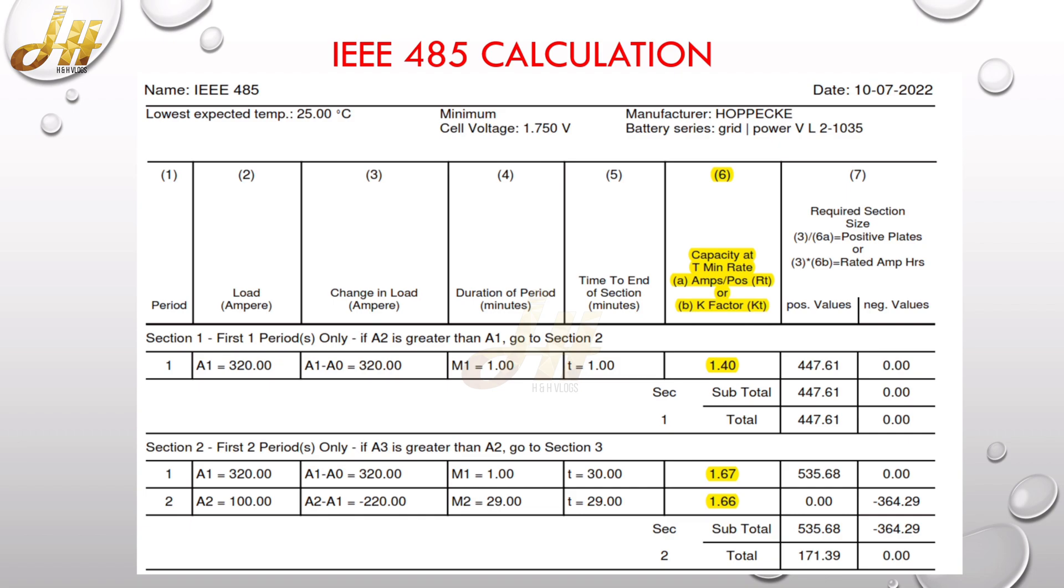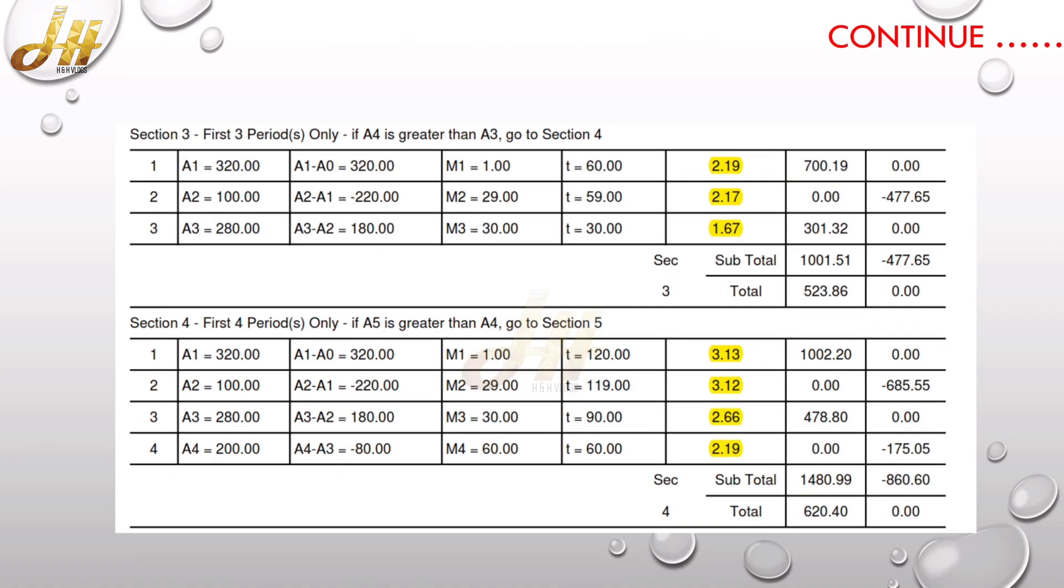Which has been highlighted in the sixth column. Now you can see the first period, which is A1 to 320 ampere, which has been for one minute, has been multiplied with the KT factor value 1.40, so you got 447.61. Similarly, for 29 and 30 minute, the KT factor values are 1.66 and 1.67.